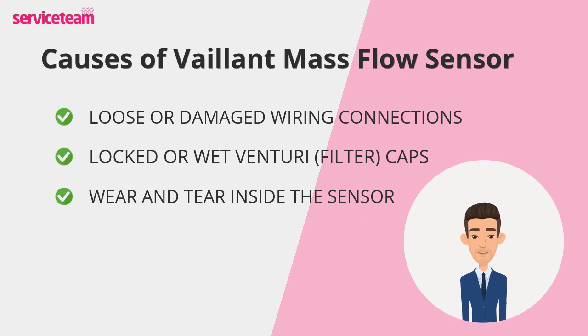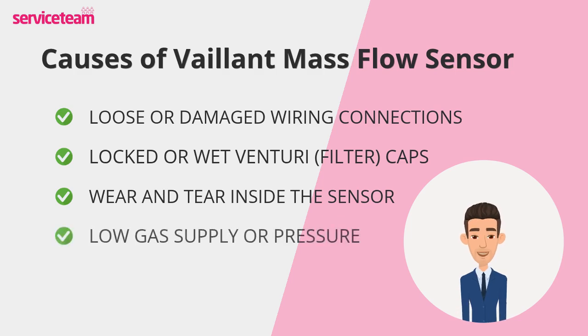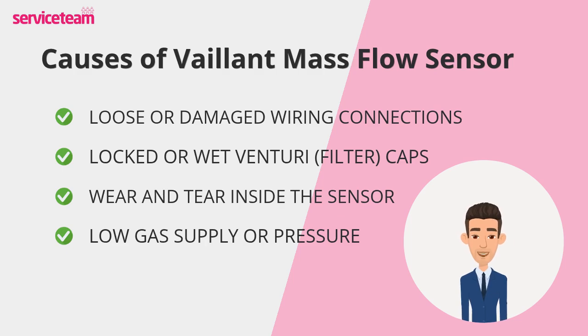The mass flow sensor monitors the fuel-to-air ratio for safe combustion. If the gas pressure is too low or inconsistent, the sensor detects abnormal flow, and the boiler may refuse to ignite or repeatedly shut down to prevent unsafe conditions.